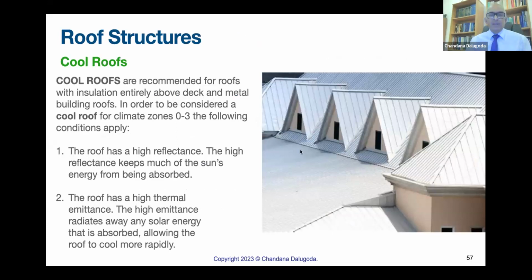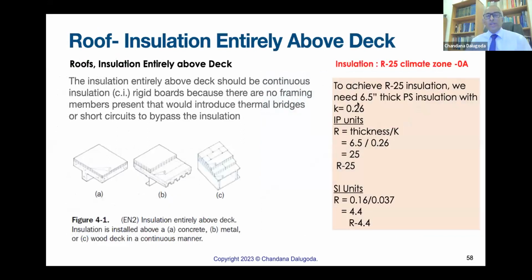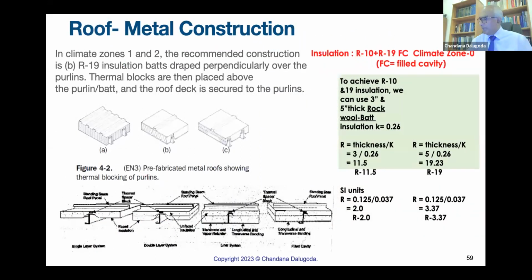Cool roofs. Cool roofs are light colored roofs which reflect solar energy. But I can't fathom why our roof manufacturers have multicolor roofs, red, green, blue. At the last techno show, I met one of these manufacturers and told them, look, don't do this. Have silver color, white color roofs for energy efficiency. Let's see if they will follow that. Now you can see roof insulation above a concrete block. To achieve 0A status, we need 6.5 inches thick insulation. Similarly, for zinc alum sheet, we need 8 inches thick insulation.